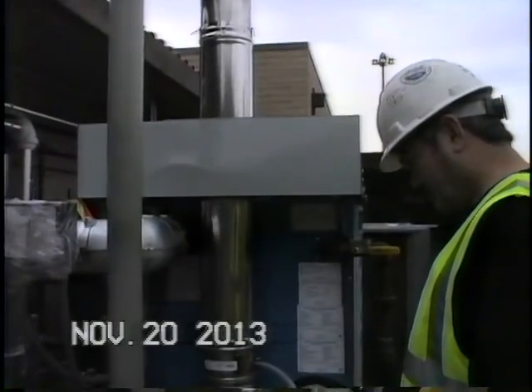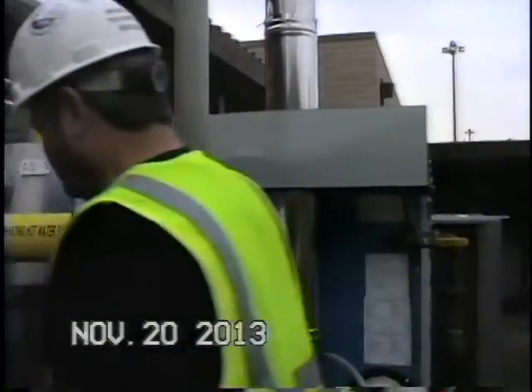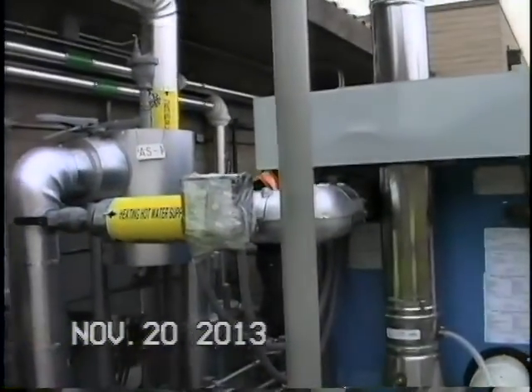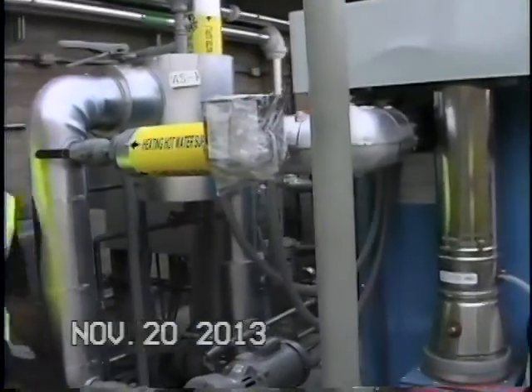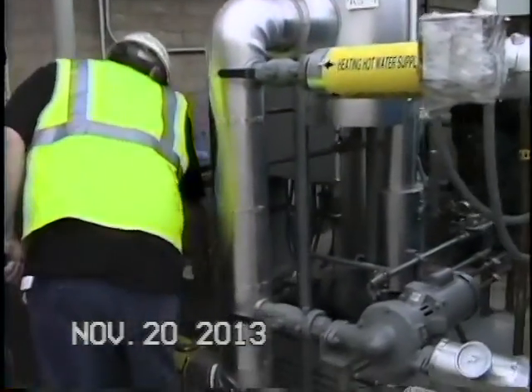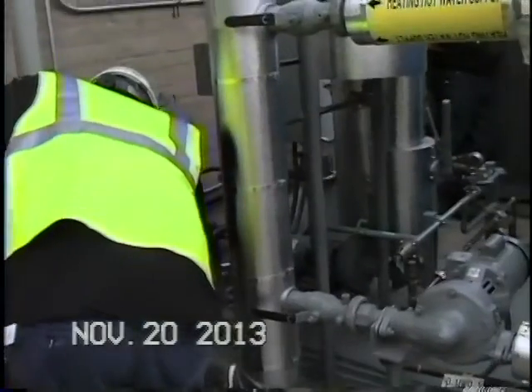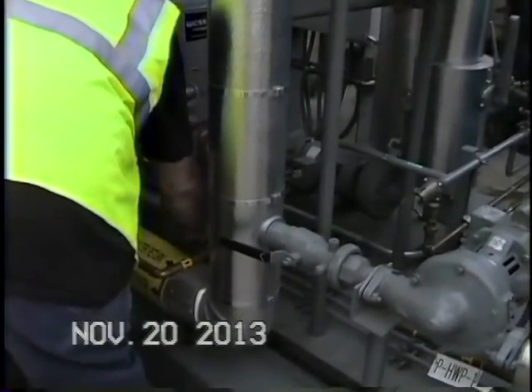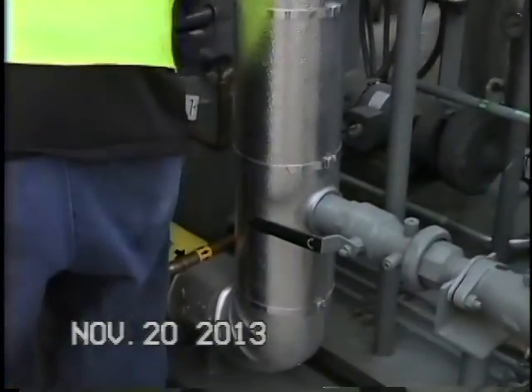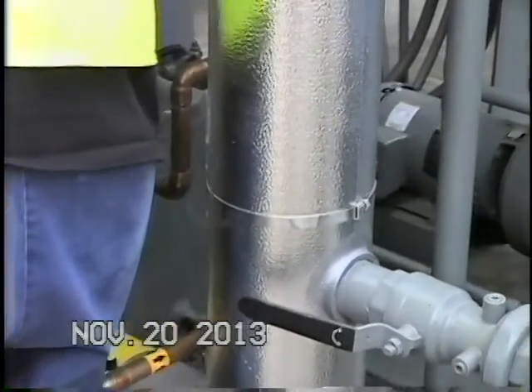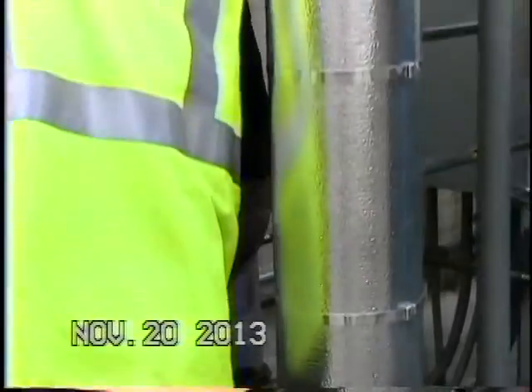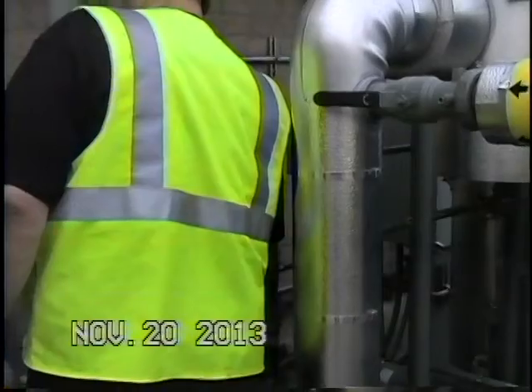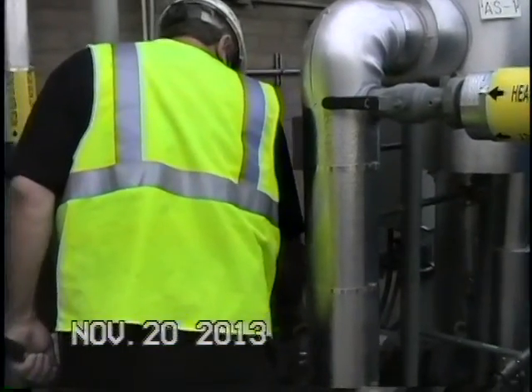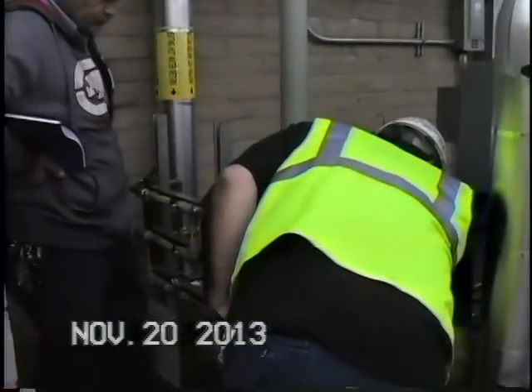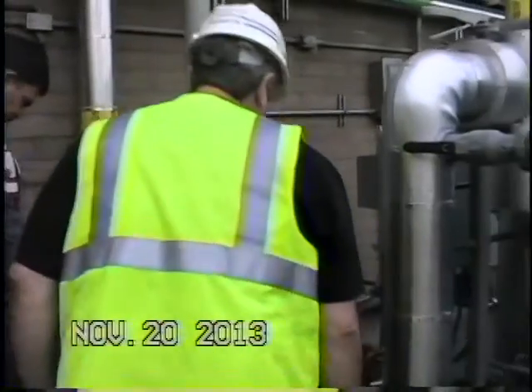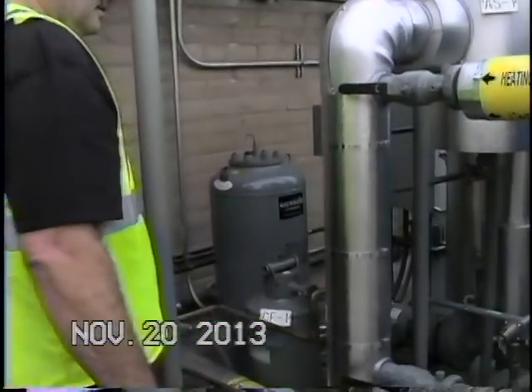How did this come off? Well, you have to isolate it first, so you have to shut this off, and this off, I'll turn this back on, and then you drain out the water here to let the pressure out. Right here, you just undo, and then it just comes out. Or this comes out. Yeah, this comes out, and then there's a gasket right there. You have to make sure there's no pressure on it. It's 180-degree water.